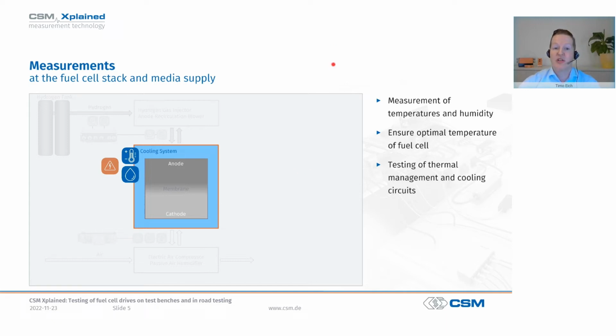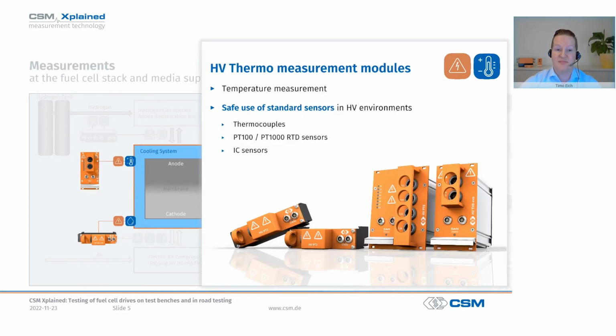Since we are working here in the cooling system with high voltages, the temperatures now also must be recorded in a high voltage safe way, and this of course requires high voltage safe temperature measurement technology. For this purpose, you could now use our high voltage safe temperature measurement technology. These modules are available for thermocouples, PT100, PT1000 resistance sensors, and also for special applications with high precision digital temperature ICs. With these measuring modules, you now measure your temperatures in a high voltage safe manner and directly send the measured data on the CAN bus.